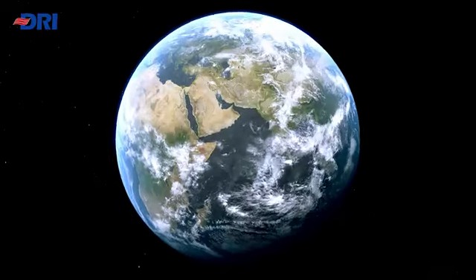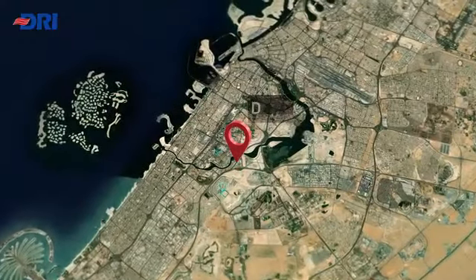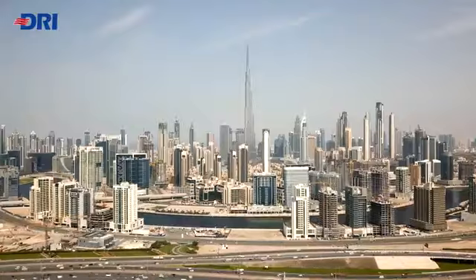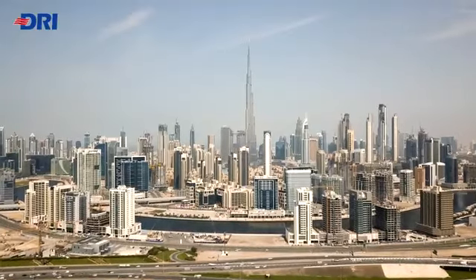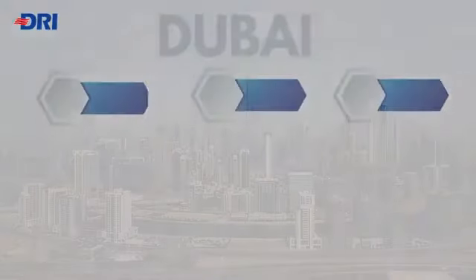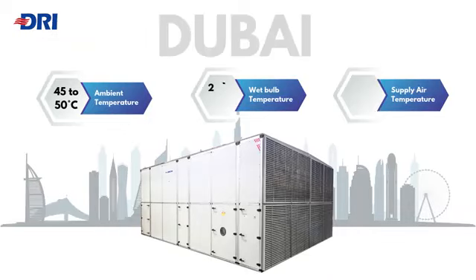Now, consider a different climate like Dubai, which experiences both high temperatures and elevated humidity levels. During peak summer, outdoor temperatures can reach 45 to 50 degrees Celsius, with a max wet bulb temperature of around 25 to 30 degrees Celsius. Despite these challenging conditions, an IDEC system can still provide efficient cooling, reducing supply air temperatures to approximately 22 to 24 degrees Celsius.